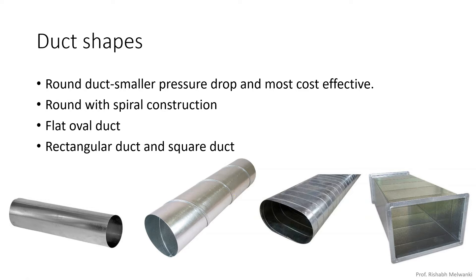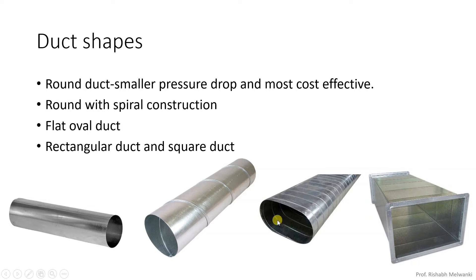Next we will see what are the different duct shapes. First is round duct, which is cost effective — especially round with spiral construction. If you even see chimneys, those chimneys have some spiral structures on the round surface. This spiral construction prevents vortex generation behind the duct, which could cause the duct to vibrate and the structure to collapse. So in order to prevent this, spiral construction has been provided. Next we have rectangular duct and square duct. Then flat oval duct, which combines the advantages of round and rectangular duct.